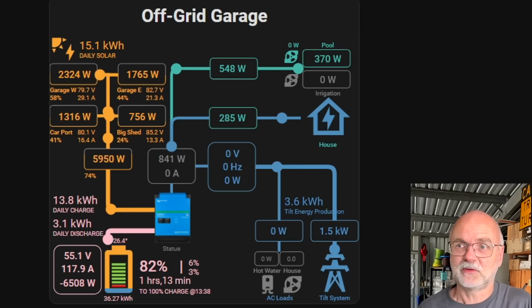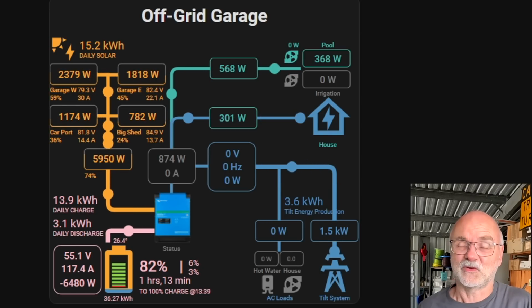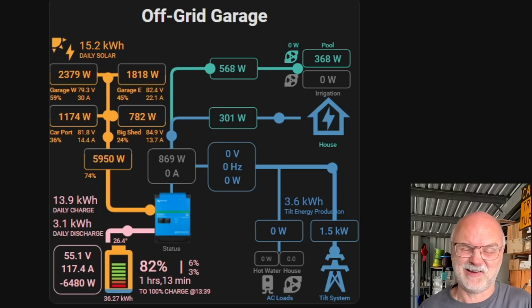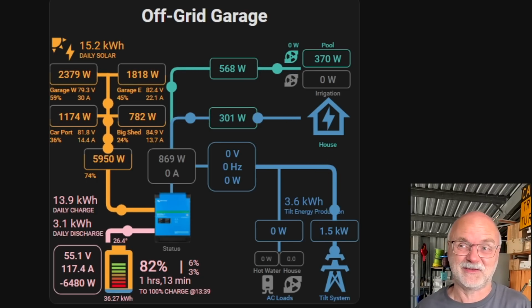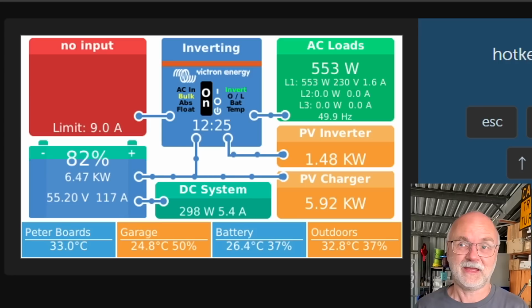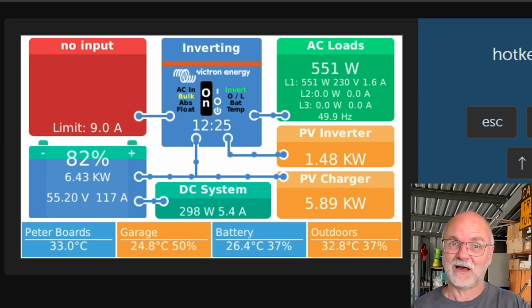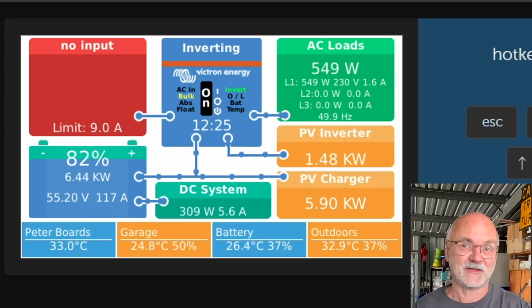We're still charging with 117 amps into this battery shelf, so it may take another half an hour at least until the current really goes down. We've reached a pack voltage of over 55 volts now. The smart shunt isn't resetting to 100% because the current is far too high — above the tail current we've set of 17 point something amps. We need to be under that current for at least 3 minutes.